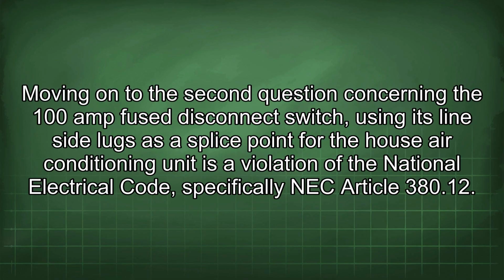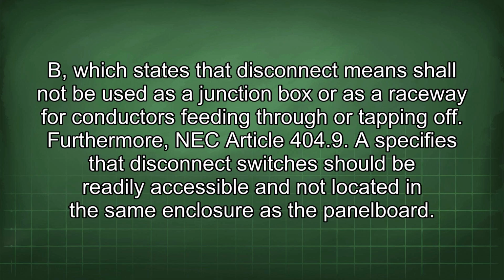Moving on to the second question concerning the 100 amp fused disconnect switch. Using its line side lugs as a splice point for the house air conditioning unit is a violation of the National Electrical Code, specifically NEC Article 380.12.B, which states that disconnect means shall not be used as a junction box or as a raceway for conductors feeding through or tapping off.